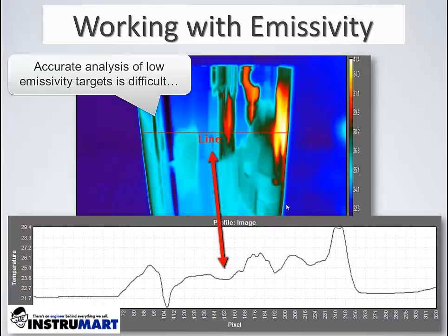Let's first, though, take a look at our stainless steel cup with our infrared camera at steady state with no hot fluid in it. The IR image presented here with its corresponding color palette and temperature scale would lead us to believe that there is a temperature variation across the stainless steel cup.